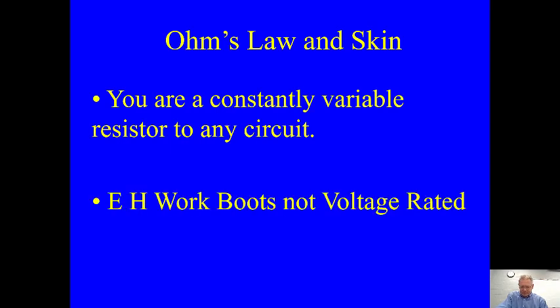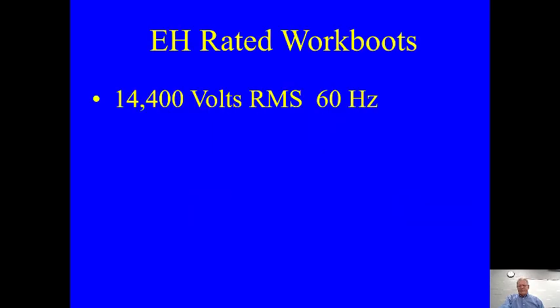EH work boots are not voltage rated. They're called electrical hazard work boots. You can look in the tongue; whenever you buy boots, it should have the EH label in there. They're tested at 14,400 volts RMS, 60 hertz, for 1 minute, and they expect less than 3 milliamps to flow through the boot. These are not EH rated, at least last time I looked.